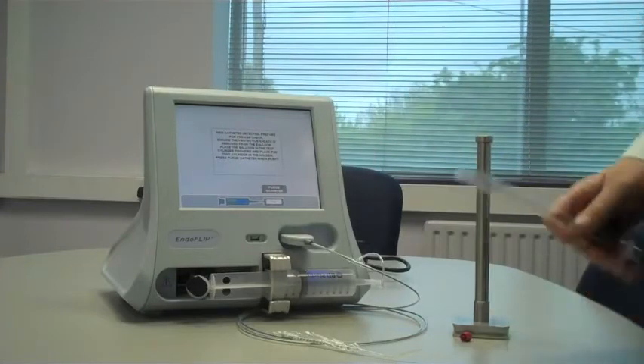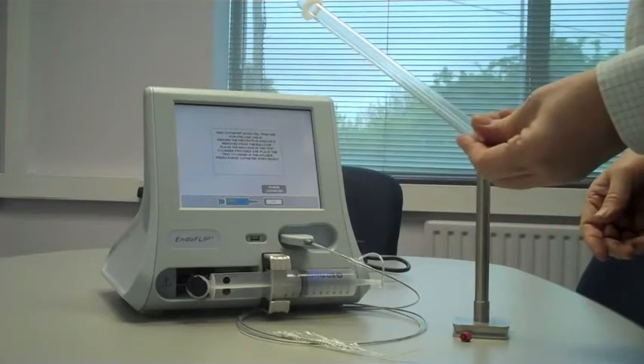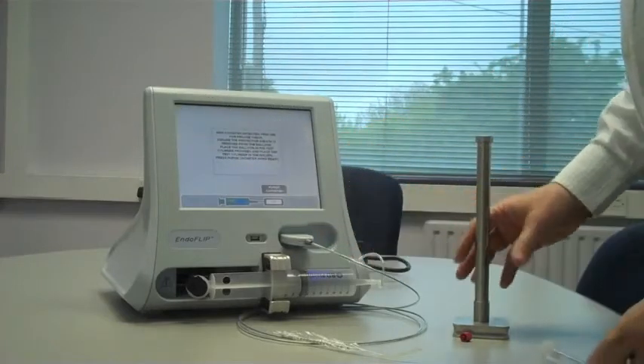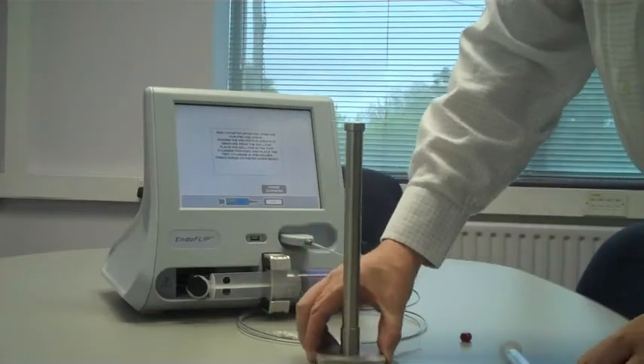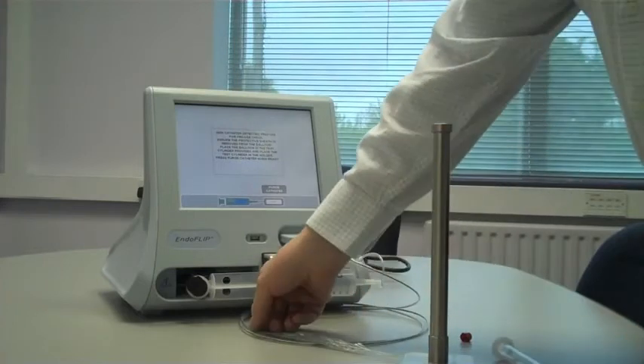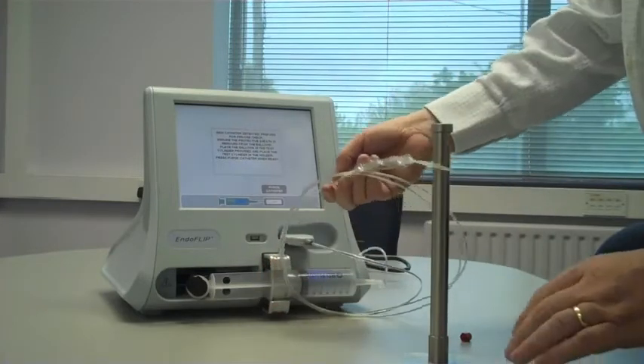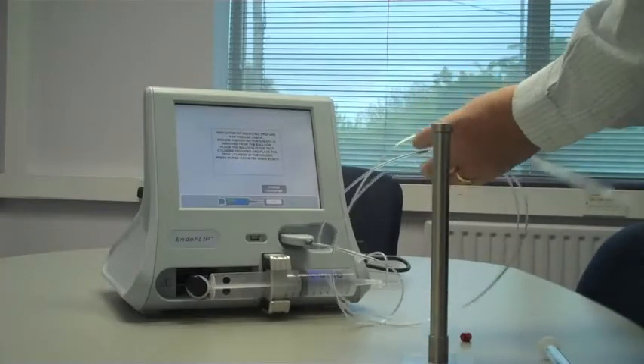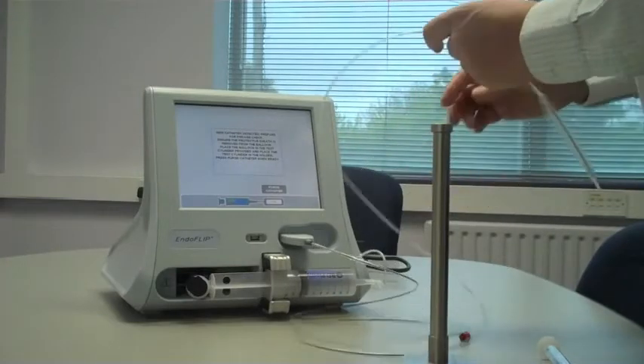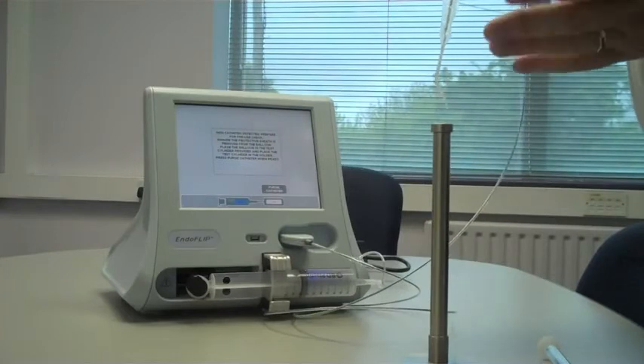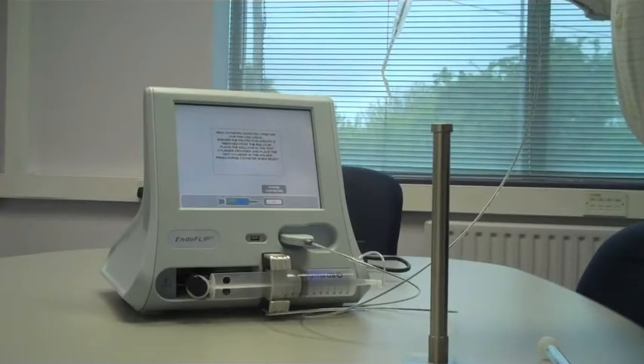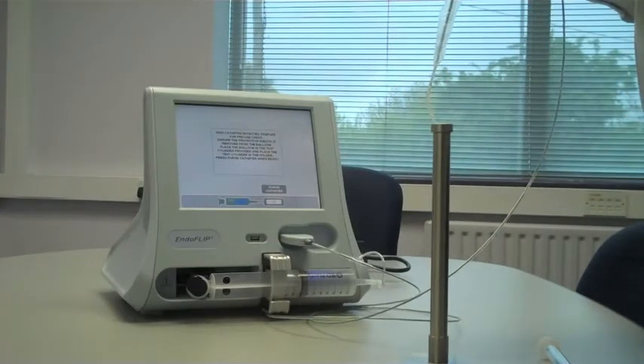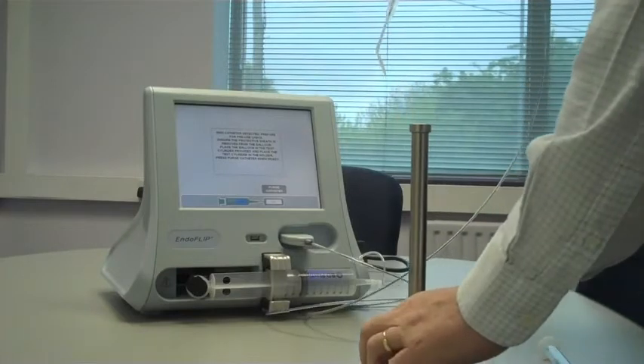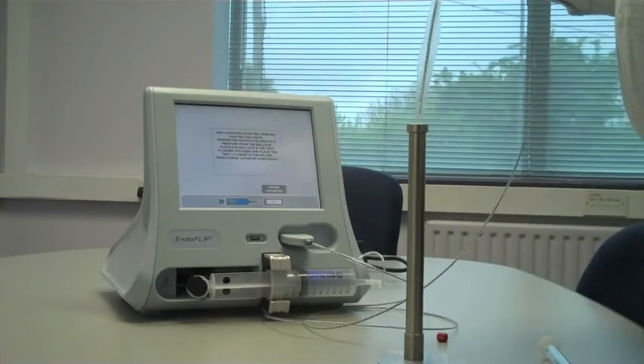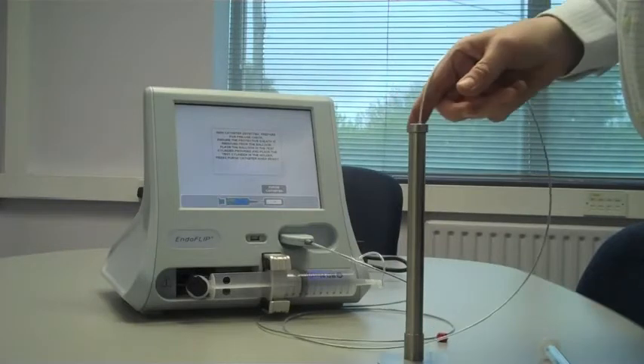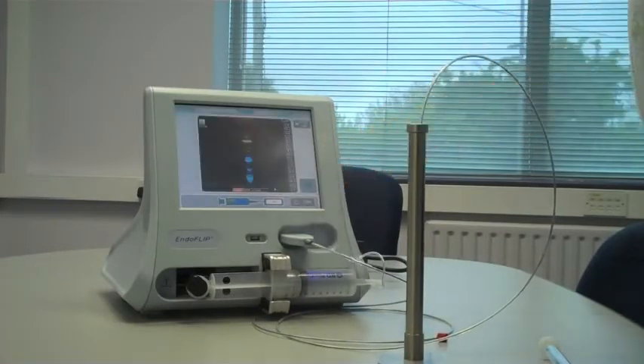Now, there are two types of cylinder. There's this disposable version here, or more recently we have this standalone metal version which comes with your machine. Essentially the purpose of this procedure is twofold. We want to check that all the electrodes are measuring correctly, and secondly we want to purge any air that is in the line in the catheter. So we place the catheter like so and hit purge catheter.